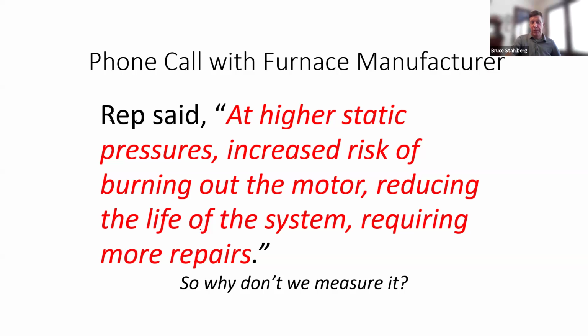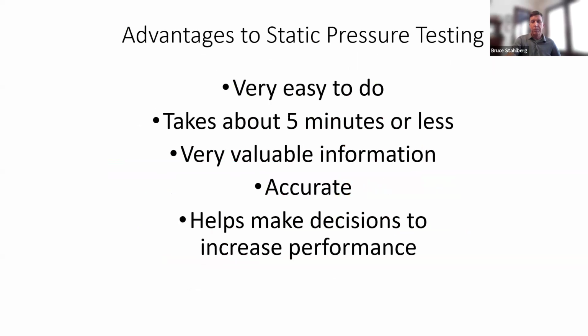So why don't we measure it? It seems like when we install a new system, we don't want to leave it in a way that's going to shorten the life of the furnace or create more repairs and more issues. There are also some other advantages to static pressure testing. It's very easy to do. It takes literally 5 minutes or less. It gives us valuable information. It's quite immediate and accurate, and it helps us make decisions on how to increase the performance.